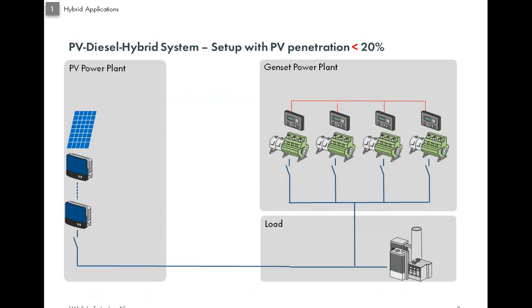Let's take an example where you want to install PV which is less than 20% of the total genset capacity. That is fairly easy to do. You do not require anything special to synchronize them. You just add the output of the PV to the load bus bars, and that's pretty much it.